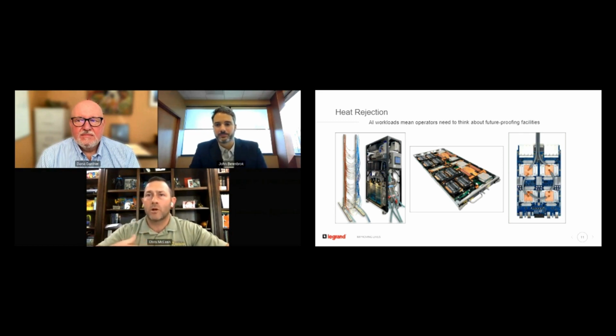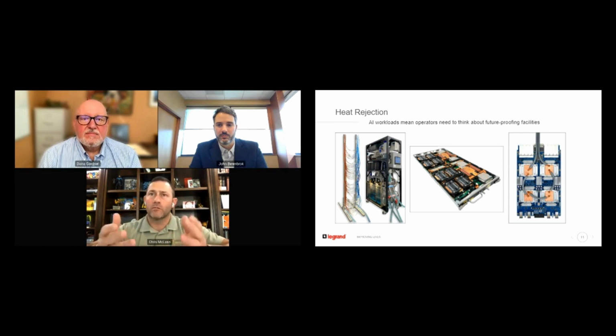But now where you're bringing chilled water directly to the rack, which is not totally different than in-row cooling units, having chilled water adjacent to the rack. I mean, certainly there's companies that have been doing in-row cooling, and Rittal has been doing water to the rack with sidecar in-row cooling for 15 years probably now. But now when you bring it directly into the rack to something like a CDU, something more akin to what you see on the left side of the slide, you have a lot more copper or some sort of piping system under the floor or overhead that's going to every single rack position. So your mechanical system costs are going way up.